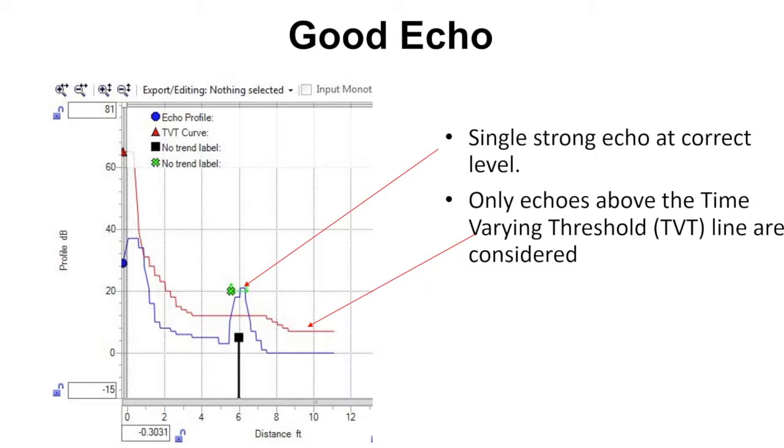The red line is what Siemens defines as their TVT or time-varying threshold line. Some people call it a mapping line. What that line tells us is that no echo is going to be considered as a valid echo unless it exceeds the red line. In this case the only echo that we have exceeding the red line is at the six foot level and that's a good echo for us.